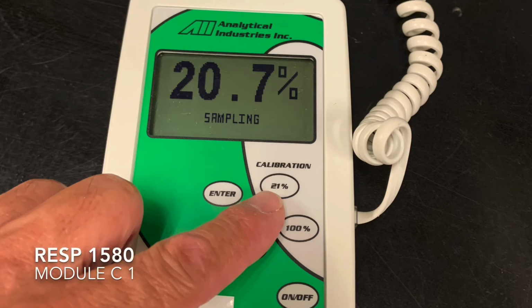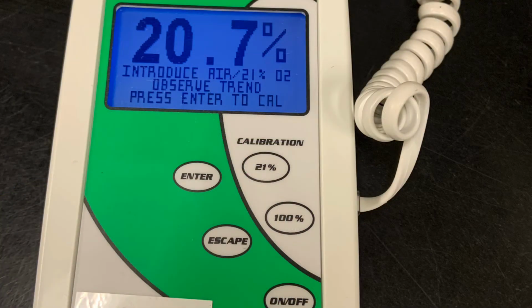Welcome to the video for the RESP 1580 lab, Module C, Station 1. And here we are looking at blenders, but in order to be able to use blenders and measure your results from blenders accurately, you need to have an oxygen analyzer. So for Station 1, we're going to be looking at calibrating oxygen analyzers. So we're going to have to start out by doing a calibration at 21%, that is a low point calibration, followed by at 100%, which is a high point calibration.